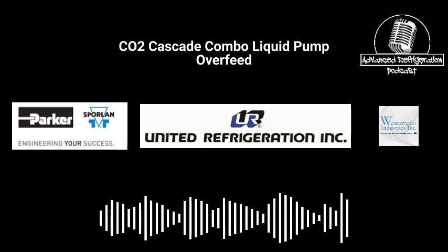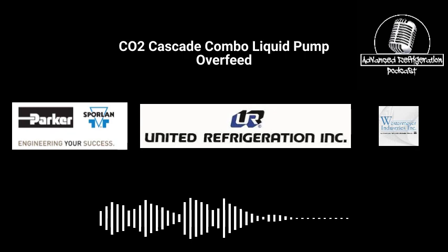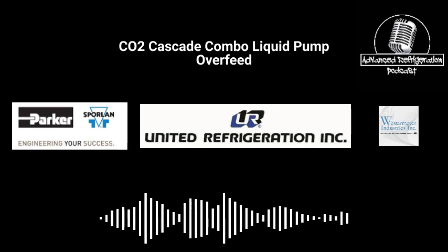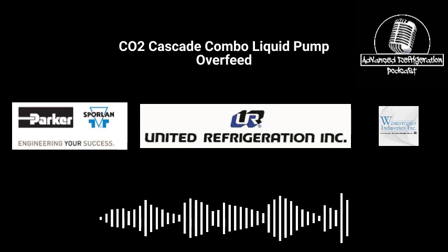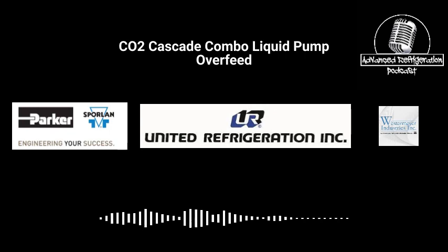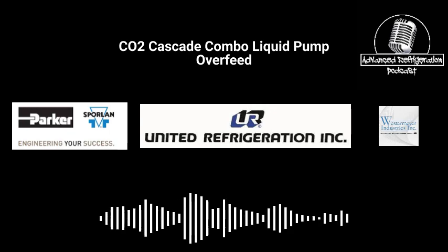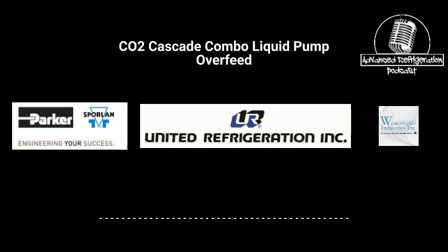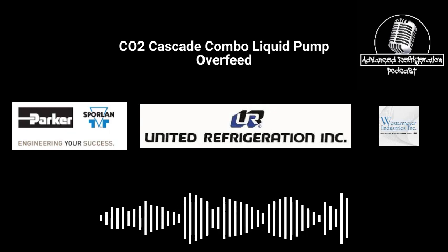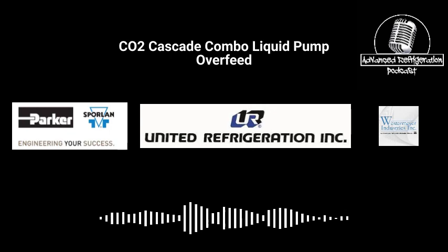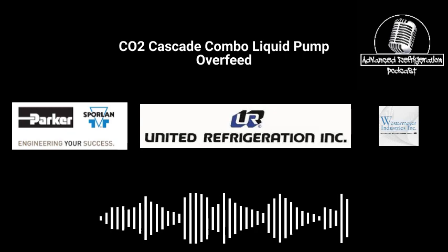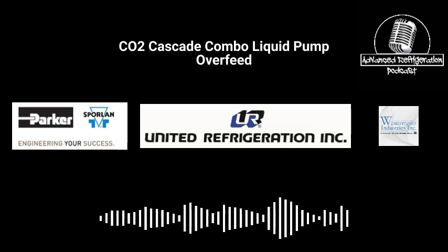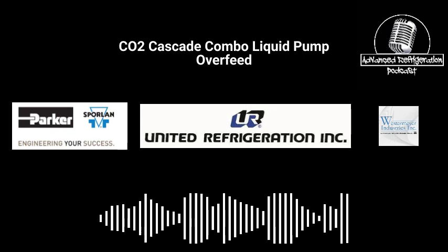The high part of the cascade system, the HFC and HFO part, is basically just exchanging the heat from the cascades out to ambient. That's all that's doing. The whole thought process here, guys, is to keep the refrigerant in one spot, just like the glycol racks. Reduce the charge, keep it in one spot, and there's less chance of that HFO or HCFC leaking in one spot than having an entire store full of refrigerant. So that's the whole goal here.